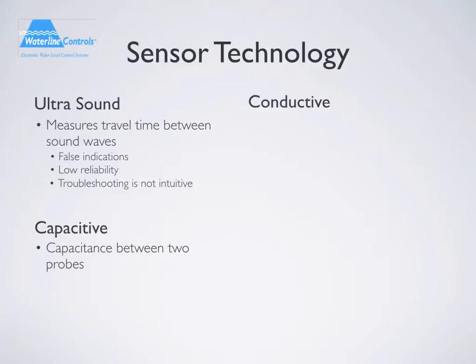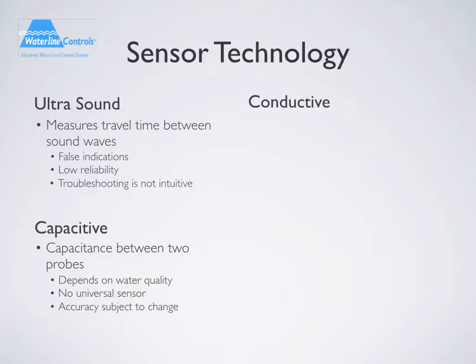Capacitive technology is designed to measure the water level in an environment by determining the capacitance between two probes. The capacitance of water depends on its quality, which itself varies between geographical regions. Because of this, it's hard to design a universal capacitive sensor. Many are sold to locations outside their intended region, causing their accuracy to fall between 10 to 15 percent. We believe this is not accurate enough to be used as a water level control — we only recommend this technology as a level indicator.